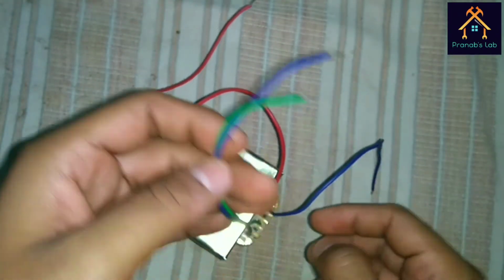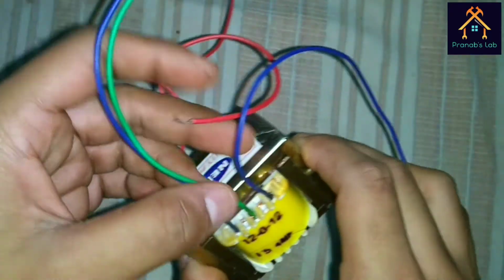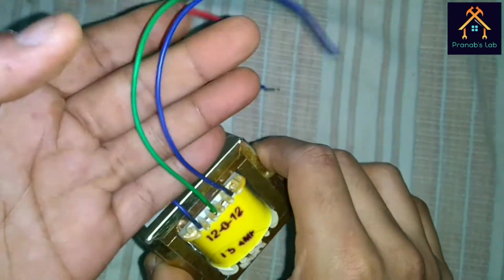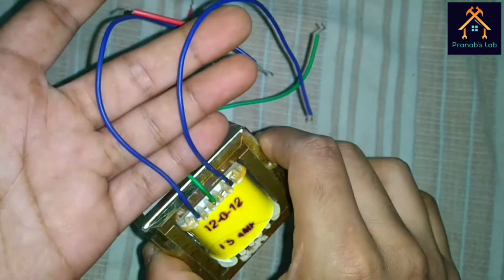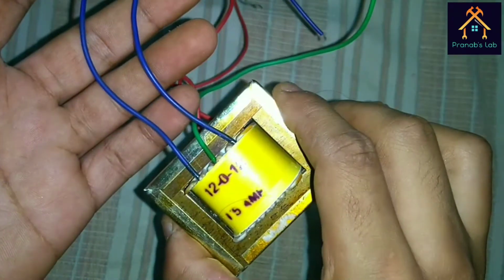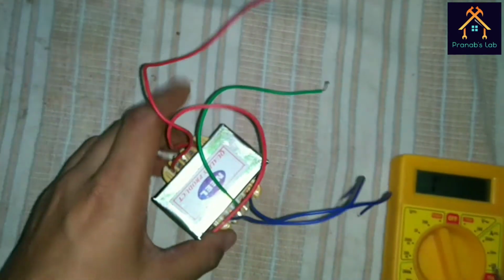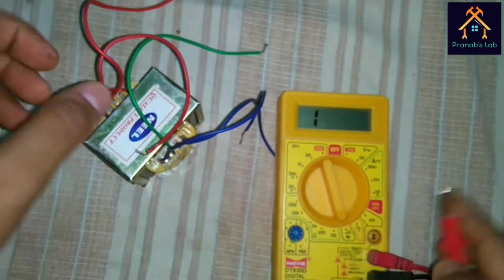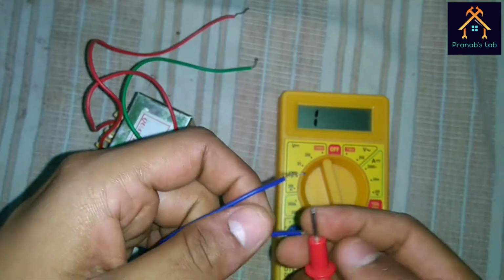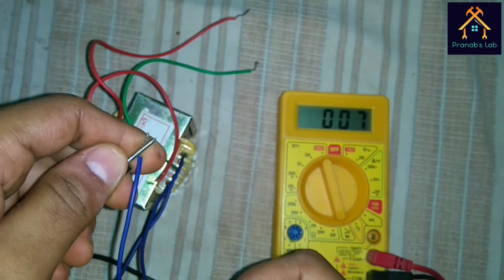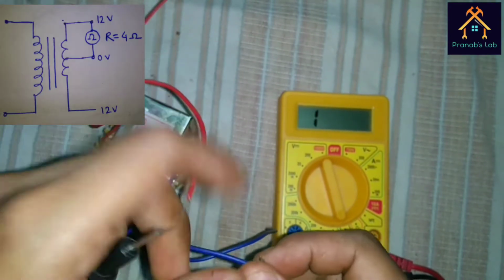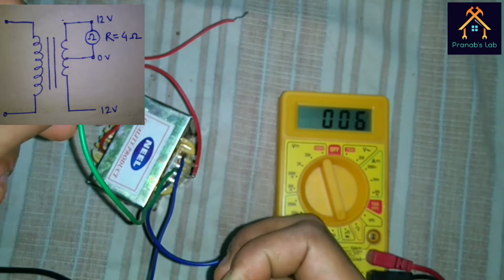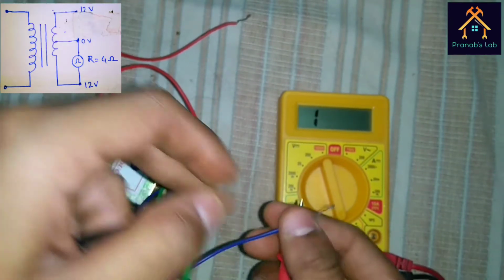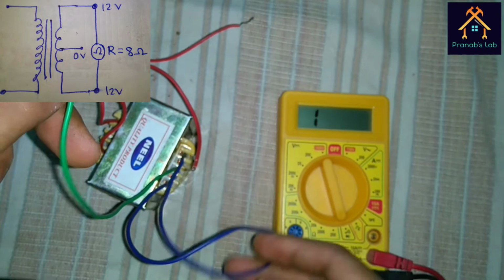It is a 230 volt to 12 volt center tap transformer, and across these two terminals we get the 12 volt output, and across these two terminals we get the 12 volt output, and across these two blue wires we get the 24 volt output. And this is the low voltage side. Let's test the continuity of this low voltage side. Actually, the multimeter is showing the resistance of the windings. This 4 ohm is the resistance of the low voltage winding because it consists of fewer turns. This test shows that the windings are okay.